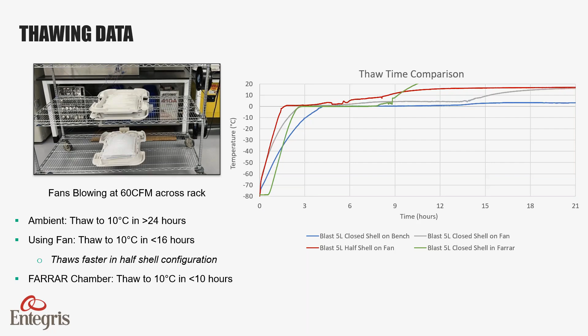So the last slide we're going to show here is just a complete freeze thaw cycle. That's something that we can do inside of that controlled rate chamber. So starting with the drug products at an elevated temperature, freezing them all the way down to -80, allowing dwell, and then executing a thaw profile that brings them up to the temperature. So you do see a little bit of variation in those shell temperatures, generally caused by position inside the freezer, but overall a very tight spread of overall variance when freezing and thawing at maximum capacity inside that controlled rate chamber.